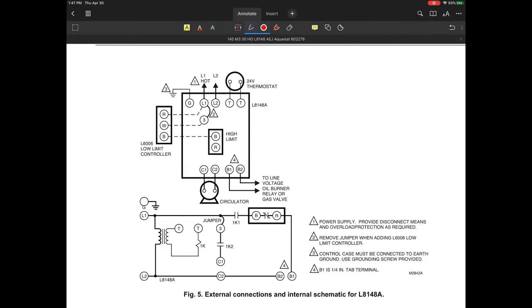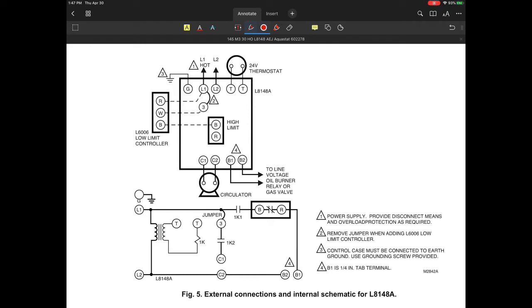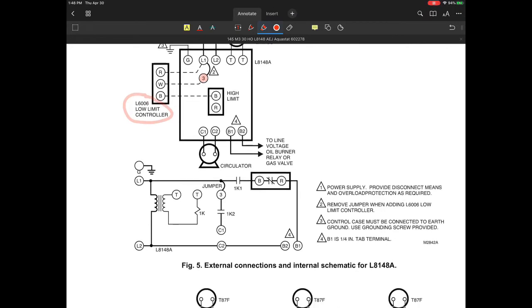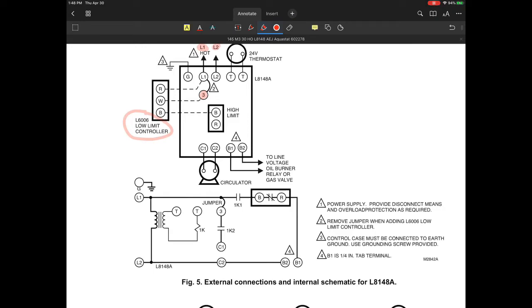All right, before we go through the E model, I want to take a look at the diagram of the A model while it's fresh in our heads. We talked about the wiring, L1 being the hot, L2 being the neutral, and then they have a terminal 3. Remember earlier when we talked about the low limit controller: that was a way to keep the boiler up to temperature so that we're not creating a problem with the application.